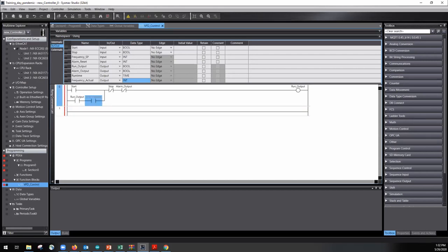Hey, Stu, I have a question for these custom function blocks. Can you force an input or an output for any of these variables that you're creating in the simulator? Do you have the ability to force those to something? We can set and reset them like we would a variable in logic, yes. But forcing them like we would an IO point wouldn't work. If I tried to force on run output, or hit set on run output, that's going to be dependent on what precedes it. So we have the same simulating and testing capabilities within the function block that we do within our ladder logic. But forcing it like an output doesn't work on either front unless it is an actual output. Does that make sense? Yep, for sure.